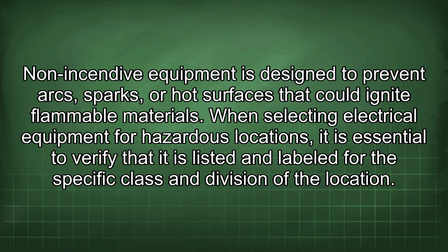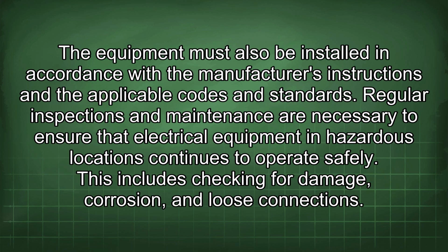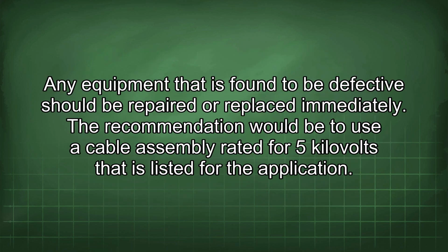When selecting electrical equipment for hazardous locations, it is essential to verify that it is listed and labeled for the specific class and division of the location. The equipment must also be installed in accordance with the manufacturer's instructions and the applicable codes and standards. Regular inspections and maintenance are necessary to ensure that electrical equipment in hazardous locations continues to operate safely. This includes checking for damage, corrosion, and loose connections. Any equipment that is found to be defective should be repaired or replaced immediately.